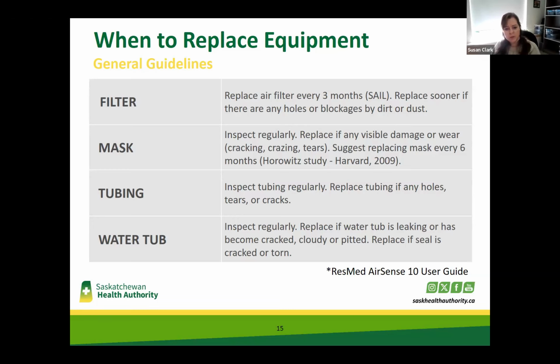With the tubing, again, inspect it regularly. As far as the manufacturer is concerned, replace it if you have any holes, tears, or cracks. And the water tub, same thing, inspect it regularly. Replace it if it's leaking. You don't want that water to get into the motor of the CPAP machine. And if it's cracked, cloudy, pitted, sometimes it's got that white powder buildup we talked about earlier, if you can't get rid of that anymore, look at replacing that water chamber.